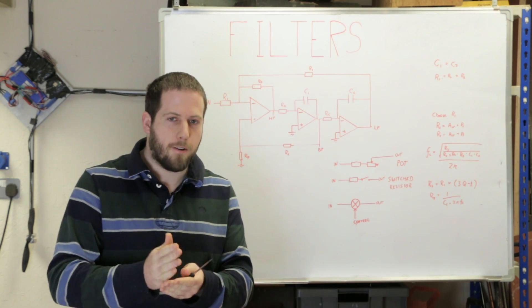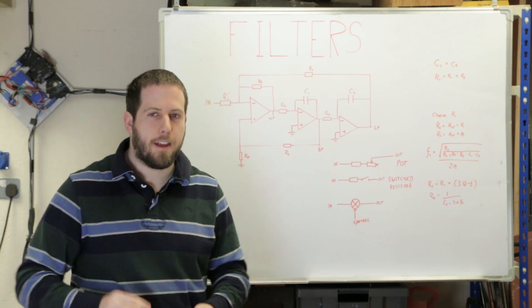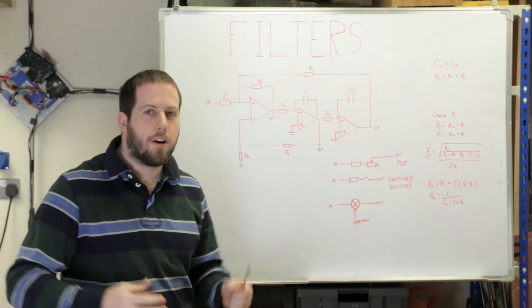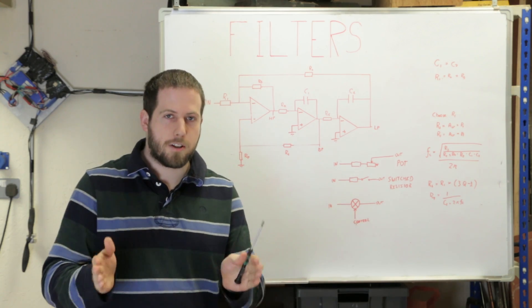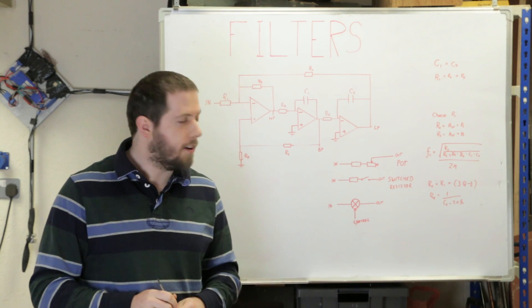If you're going to turn it on and off for 1 percent of the time and for it not to affect the overall output, that's got to be a really fast switch. So generally this tactic only works at lower speeds and you'll find a restriction on how many decades you can switch.